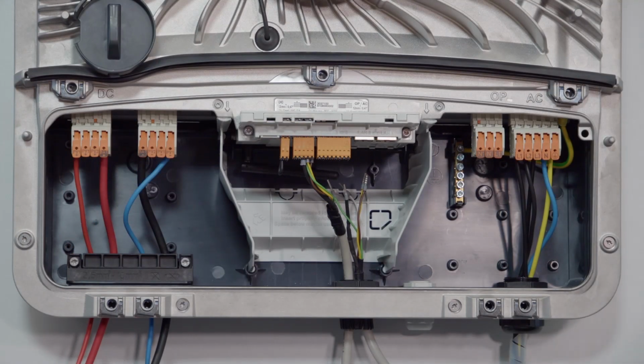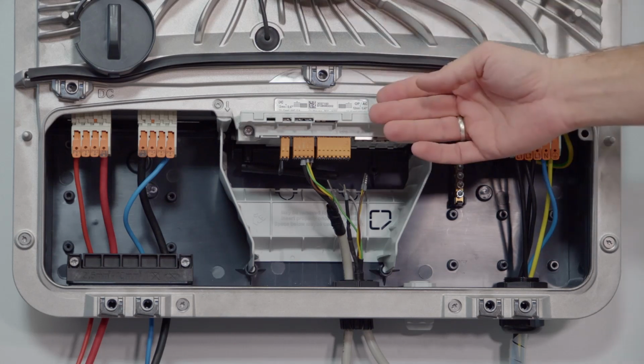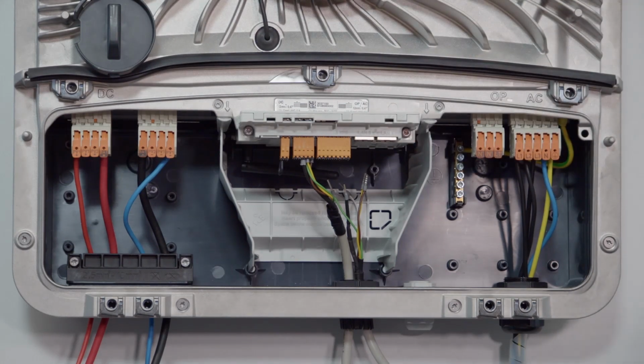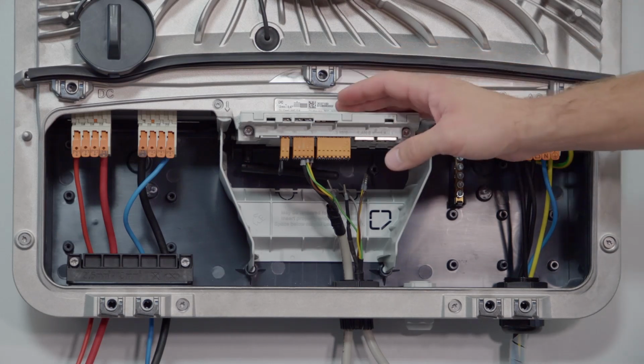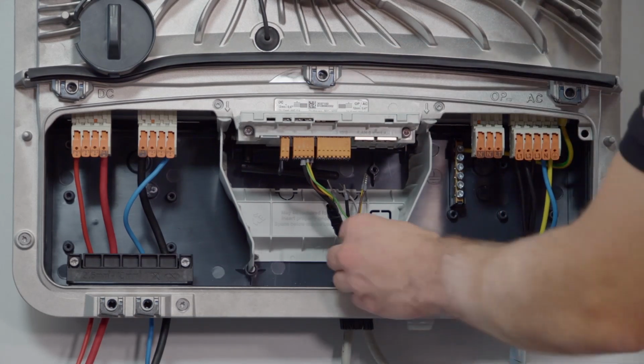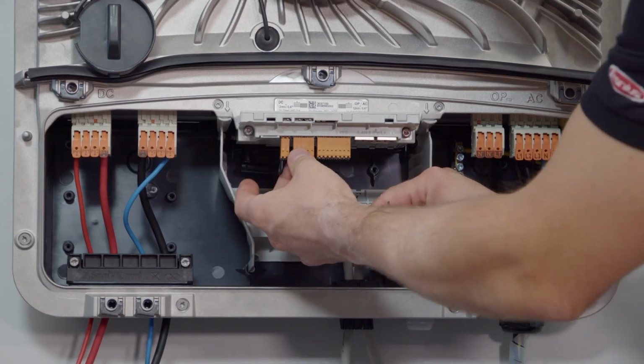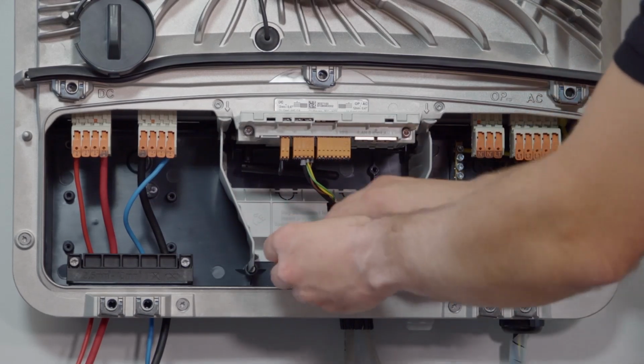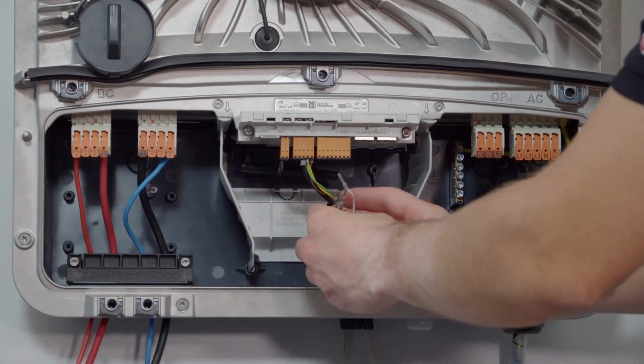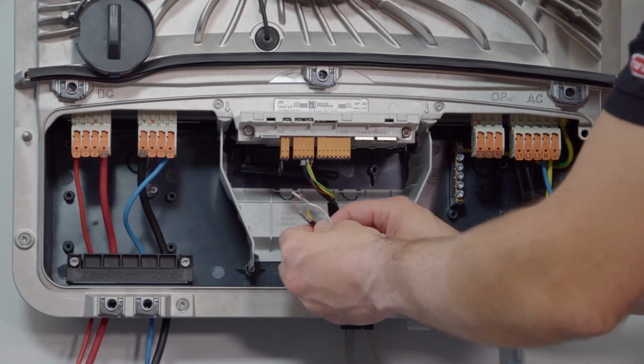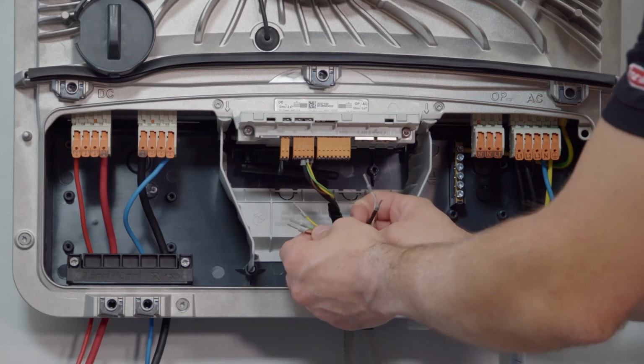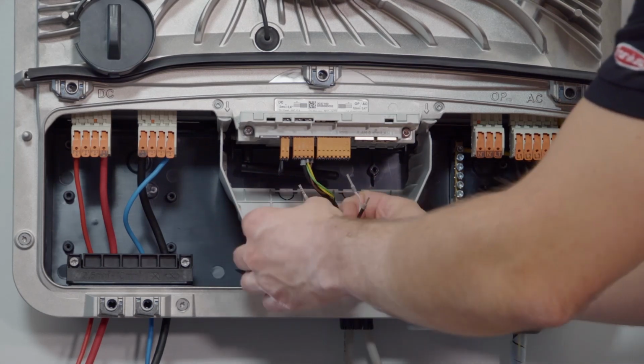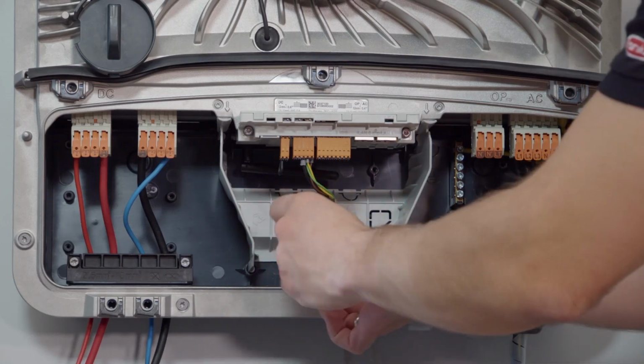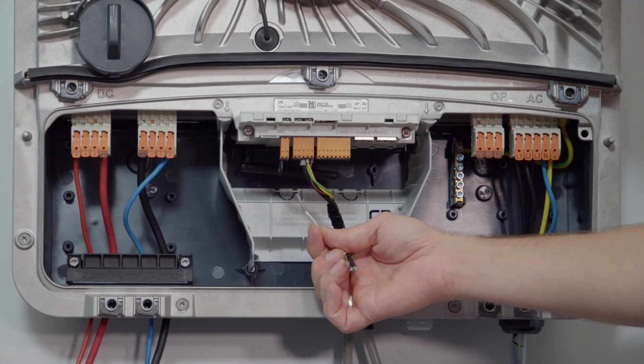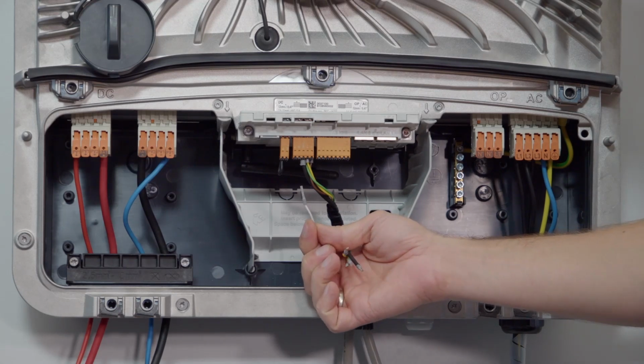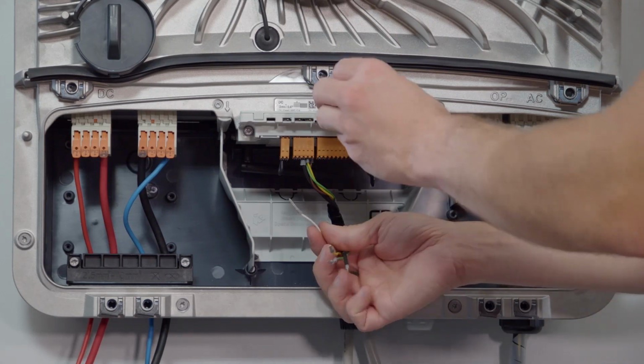Okay, so now our second step is the data communication between the GEN24 Plus and the LG battery. Therefore we are going to start at the GEN24 Plus, and with our data communication web interface we are going to start here with the plug again. So for the data communication between the GEN24 Plus and the LG battery, we again need an extra Modbus RTU cable, and therefore we have again our 4 pins, data plus, data minus, ground, and extra to that we need a 12 volt cable.